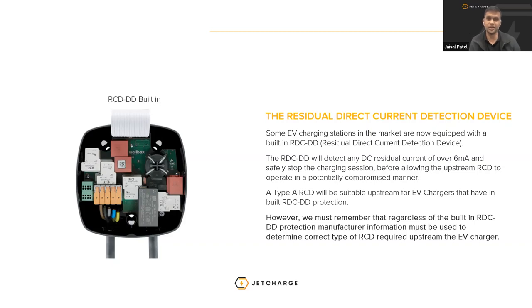So just like I said earlier, regardless of the built-in RDC-DD protection, manufacturer's information will always supersede your judgment when it comes to designing these systems. So always check the manufacturer's information. For example, the Schneider EVLink, one of the most popular EV charging stations here in Australia, does not come with built-in 6 milliamp DC fault protection, which means that we have to install a type B RCD, which is very difficult to retrofit if you have specified a type A RCD for that charger. Next slide, please.